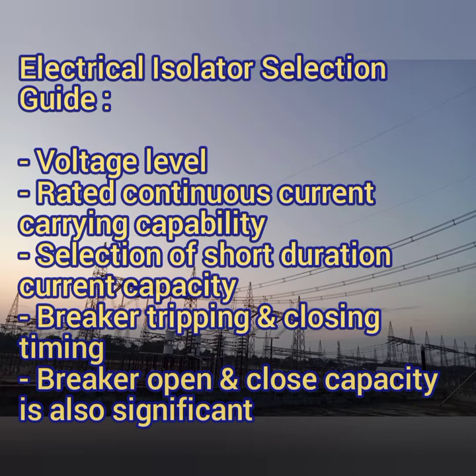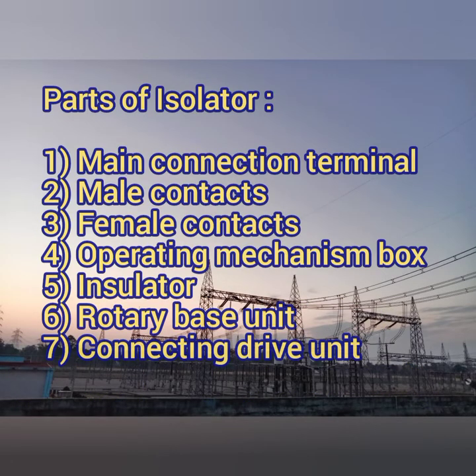Selection of an isolator depends on the voltage level of the system, the rated continuous current carrying capacity, short duration current capacity, breaking and closing timings, and breaker opening and closing capacities. The main parts of an isolator include the main connection terminals, moving and fixed contacts (male and female contacts), operating mechanism box for motorized operation, insulators to support the isolator, a rotary base, and connecting drive shafts.